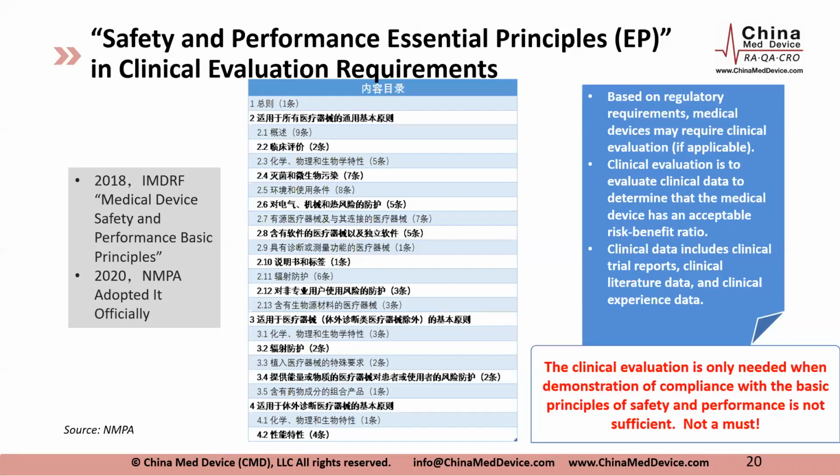So for class 2 and class 3, before we get into what clinical evaluation pathway you should go under, before you do that, NMPA has this important document that is also part of the international guidance. The 2018 IMDRF has the medical device safety and performance essential principles. And NMPA adopted this EP, the Essential Principles for Safety and Performance, in 2020. There is an English version as well.